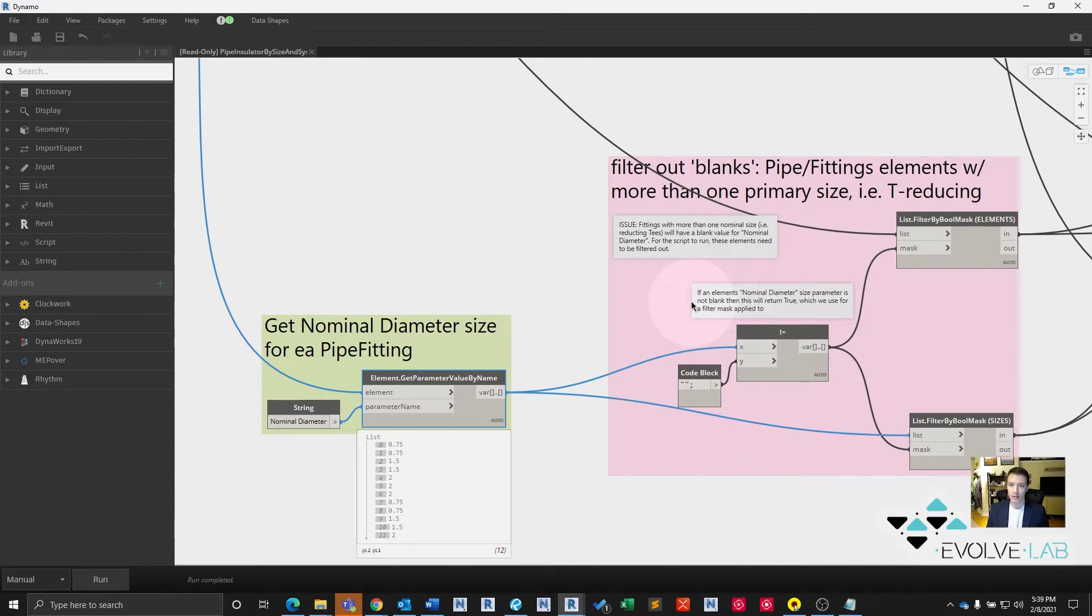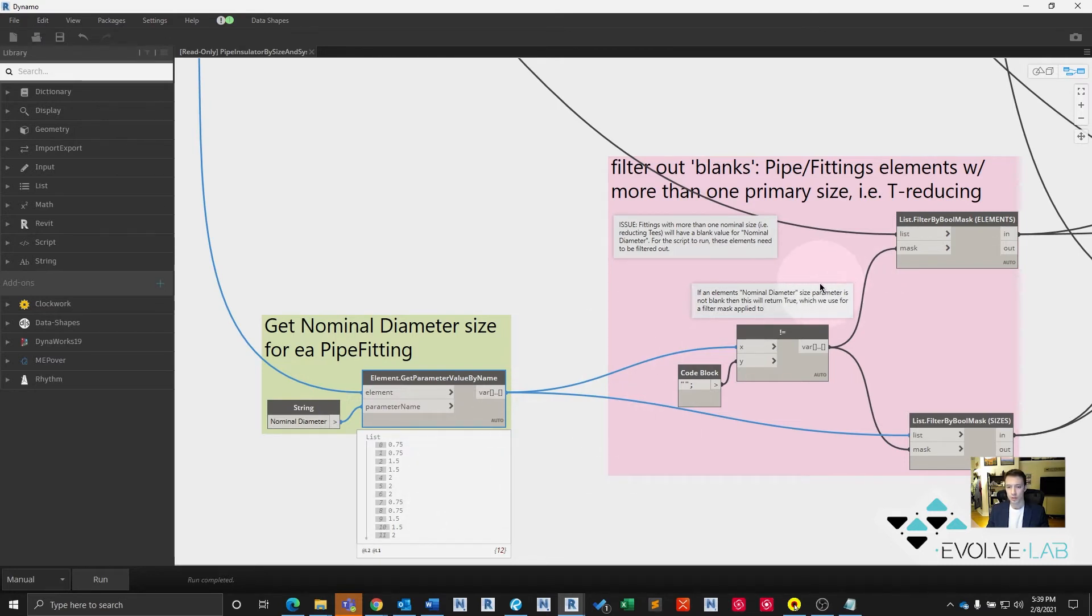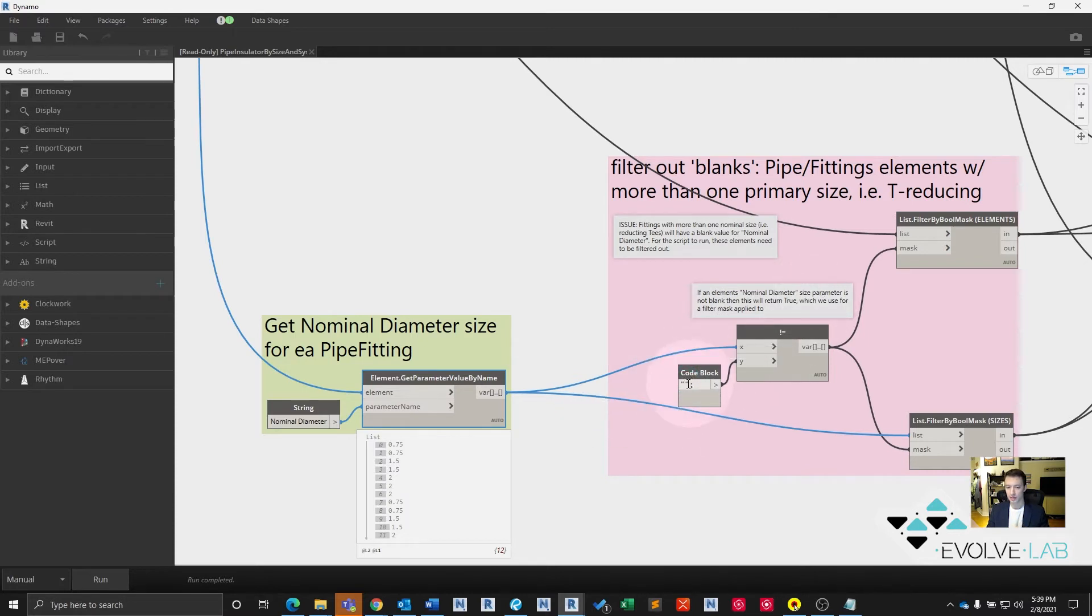And then we have to filter out blank results. So where that happens is if you have, let's say, a T-fitting that reduces, it's a T-reducing. Its nominal diameter isn't going to be just one size then, now it's going to be two sizes. You're going to have a two inch inlet and a one and a half inch outlet, let's say. And that screws up the sizing here. So for this script and this instance, we're going to filter out anywhere that returns a blank value for its size or in its nominal diameter parameter.